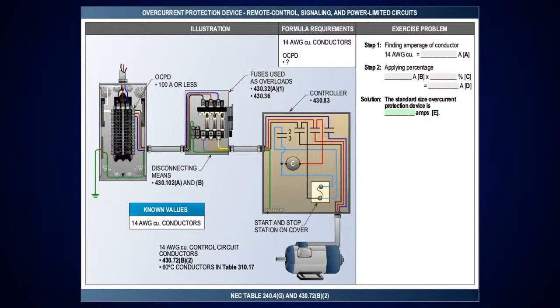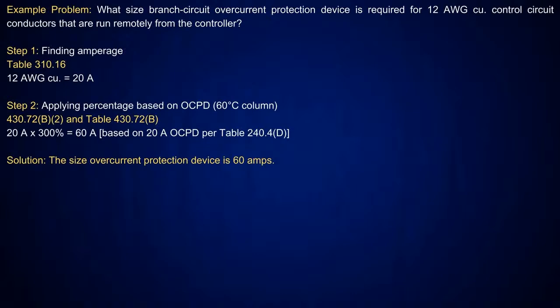And you'll be able to size it, and remember to drop down to the next standard size. Now, this is one where I'm running remote from the controller. Same exact conductors and everything, but look here, now I'm using table 310.16. It's good for 20 amps, and it's going to tell you to take it at 300%, which equals up to a 60 amp overcurrent protection device.